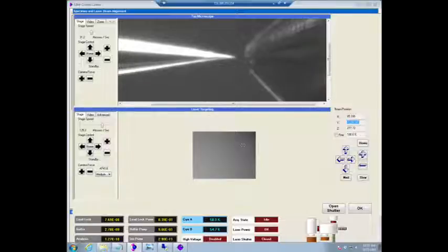So whenever you move the local electrode, you might be changing the electrode, or the other thing that might happen is that you get bad contact with the electrode. Sometimes you don't get the pulses through. Just pull it out, put it in again, and then you need to realign everything as well. Because it's not just where the electrode is, but everything has a little bit of play in a UHV system, so it will never quite end up at the same position.